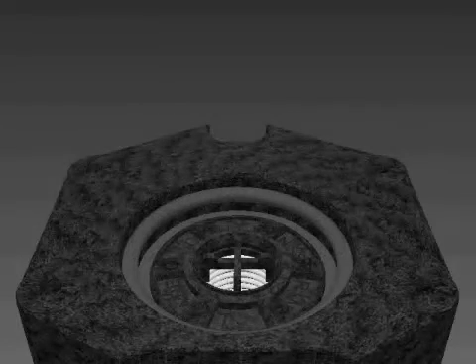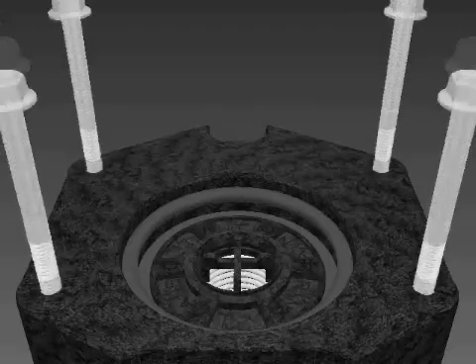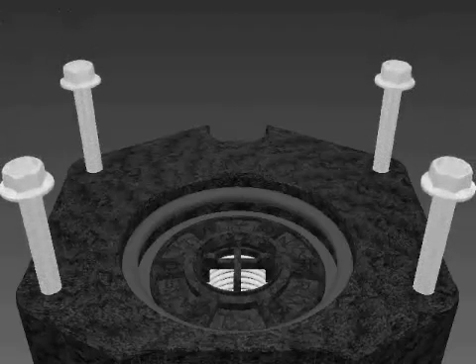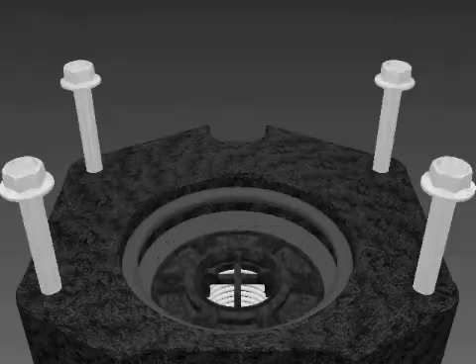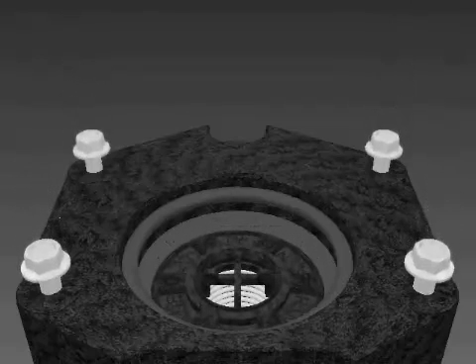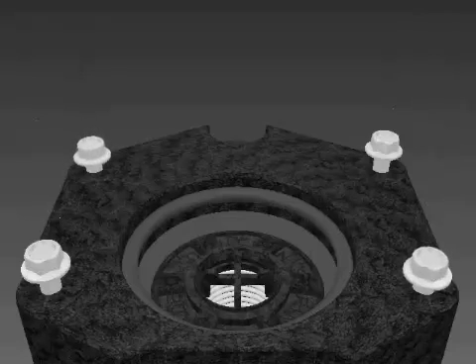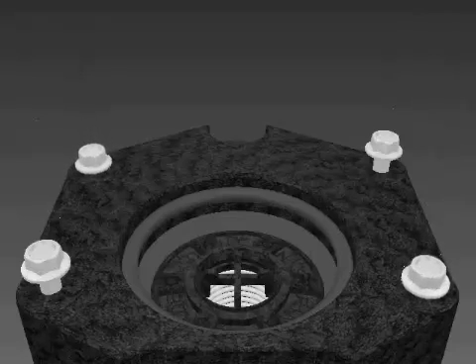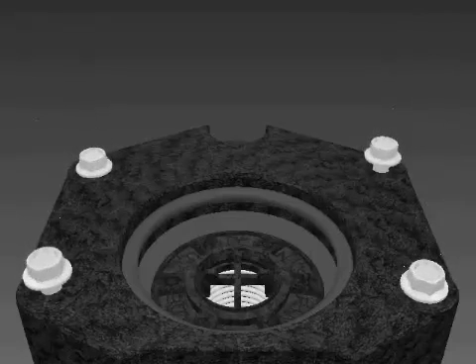Next, you will drop the four bolts into the cover. Push down on the seat of the cartridge with a thumb until it bottoms in the cover to align the diaphragm holes. Then tighten two opposite bolts. Release the seat and tighten the two remaining bolts.